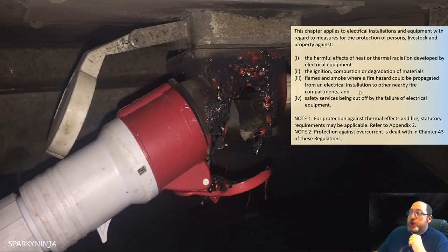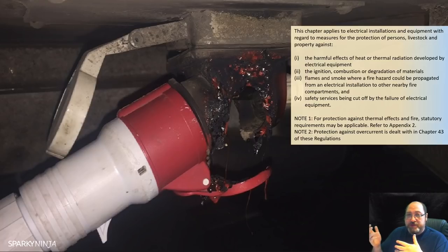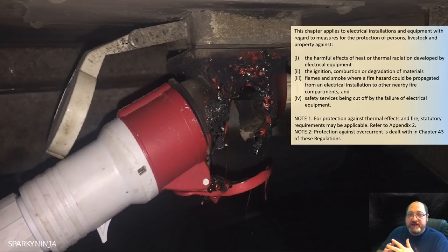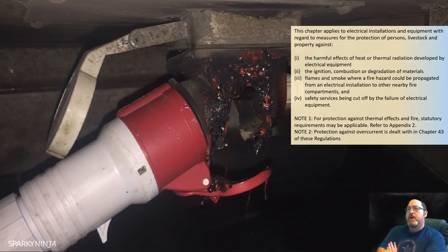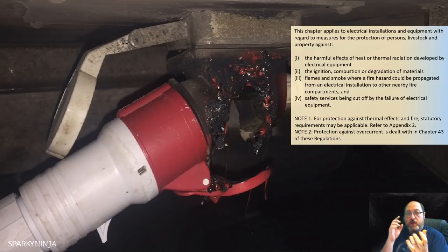We also consider flames or smoke where a fire hazard could be propagated from an electrical installation to other nearby fire compartments. We must consider compartmentalization and how the building handles fire — there are issues with smoke traveling within a building. We also need to ensure safety services are not cut off by failure of electrical equipment. If equipment fails due to a thermal effect such as a fire, a safety service must not be disconnected — think about emergency lighting.